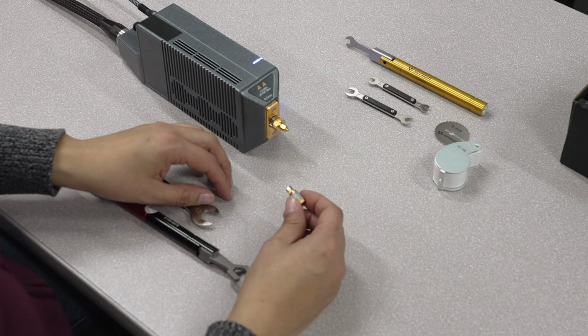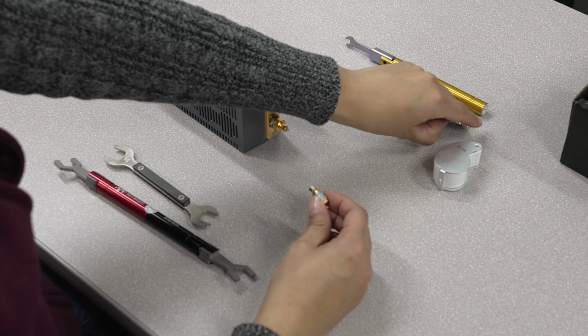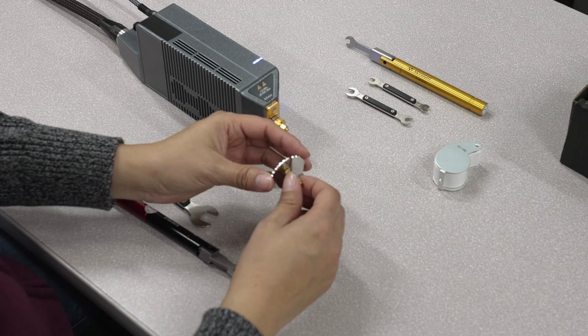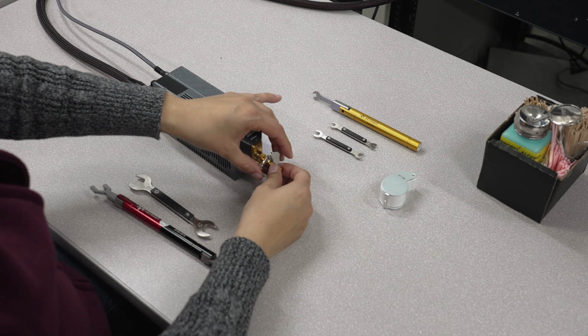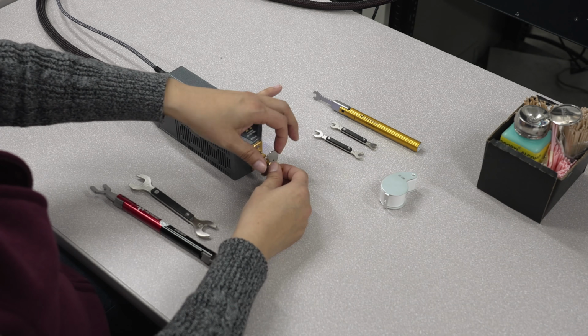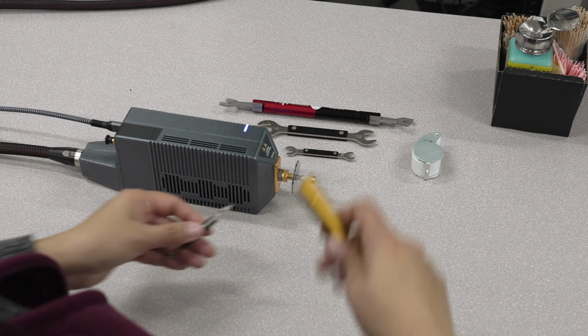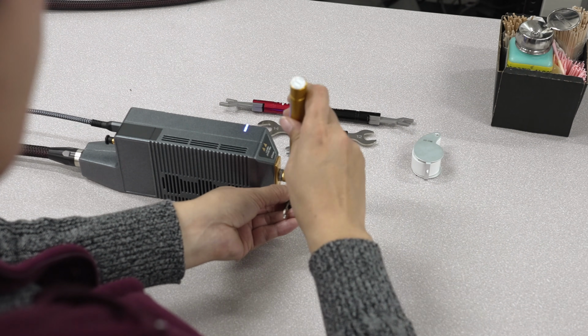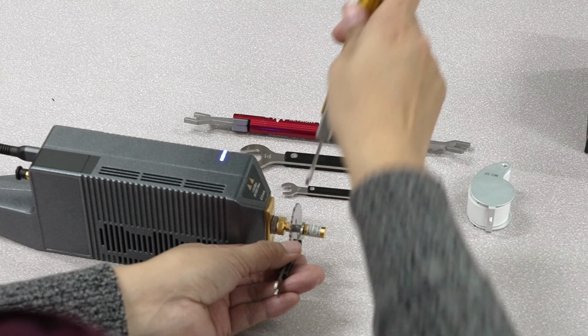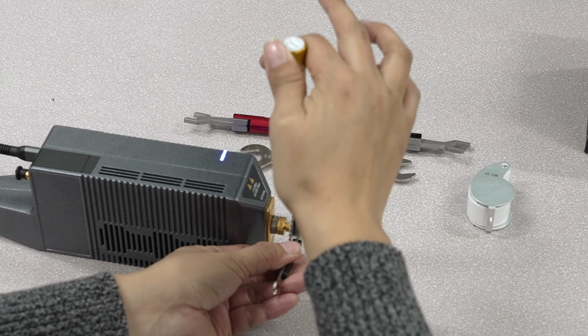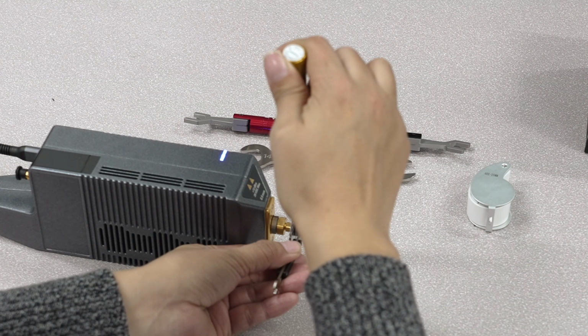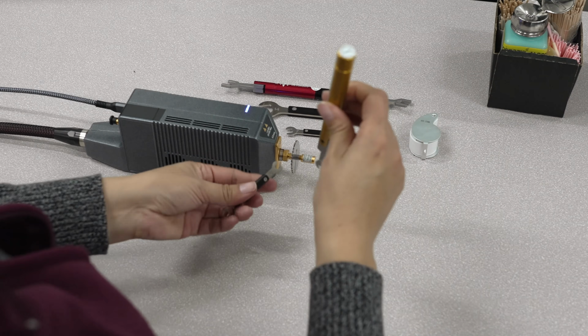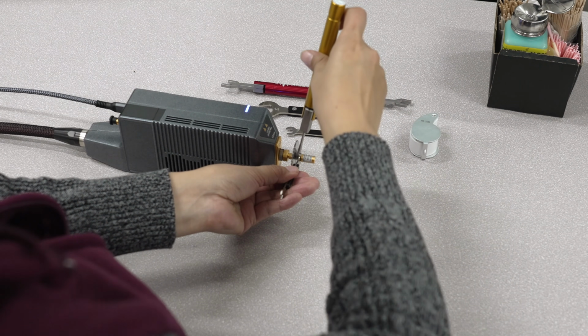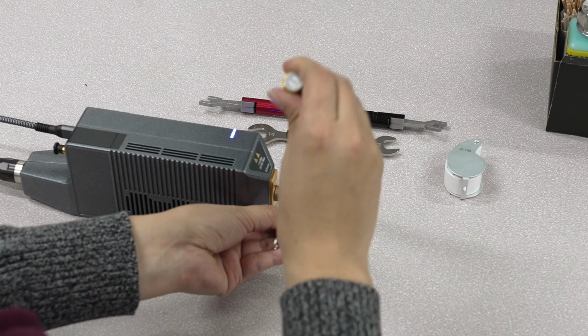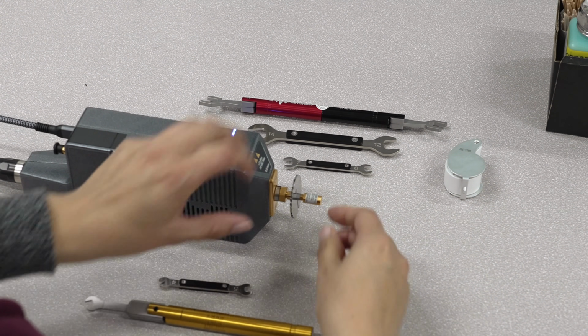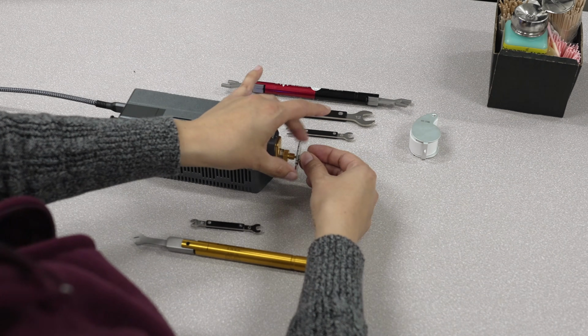For 0.5 mm male standard devices, an ergonomic nut spinner tool is included in the 0.5 mm precision calibration kit. Place this on the nut before the connection and use it while threading. Select the correct back-off wrench to fit the flats on the device and the gold 3 pound-inch torque wrench. Place the back-off wrench onto the flats and preload it. Hold the torque wrench at the appropriate angle and location on the nut. Apply torque just until the wrench starts to break. To disconnect the device, preload the back-off wrench and turn the nut using the torque wrench in the opposite direction. Finish unthreading by hand and pull the device straight back to avoid damaging the center conductor.